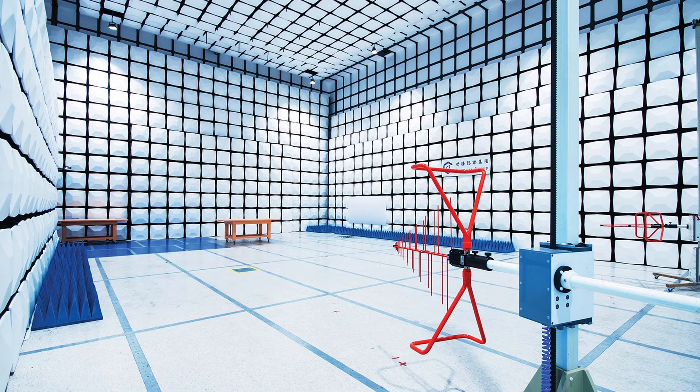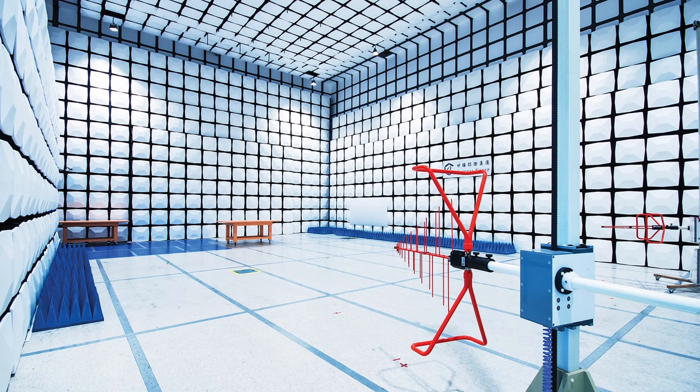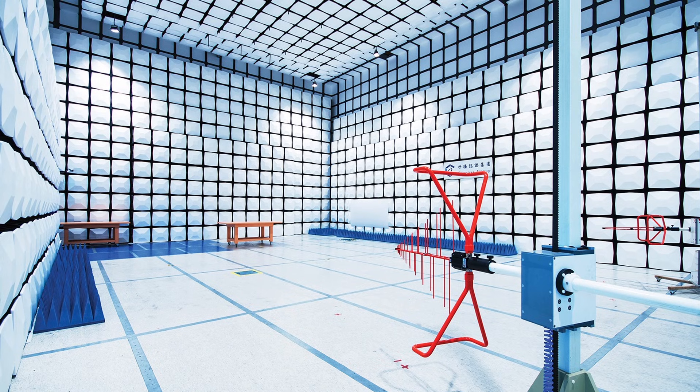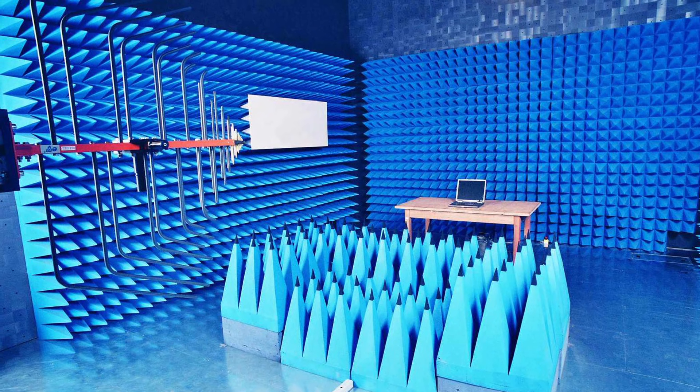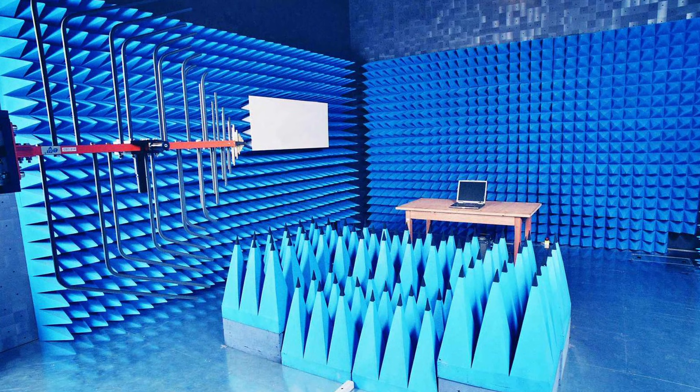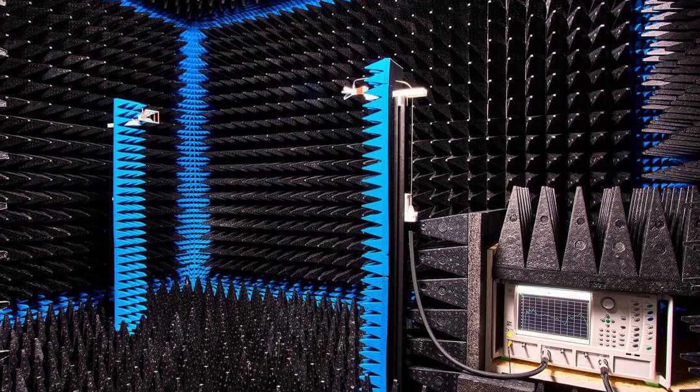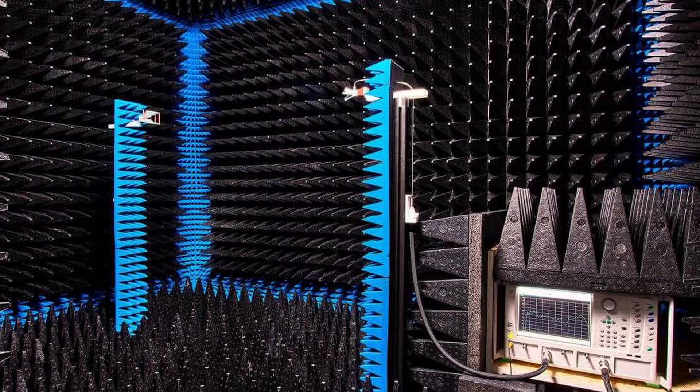The way you verify that your device is meeting these standards is by testing it in a certified EMI chamber, also referred to as an anechoic chamber. This is a room that has been specially built to absorb electromagnetic waves, so not only can no electromagnetic waves get out, but none from outside can get in — if you walk in there carrying a cell phone, you'll lose reception. The purpose of the EMI chamber is to create an environment free from any outside influence so that engineers can adequately test their devices. There are separate tests for radiated emissions and conducted emissions, each with their own unique test setup procedure.